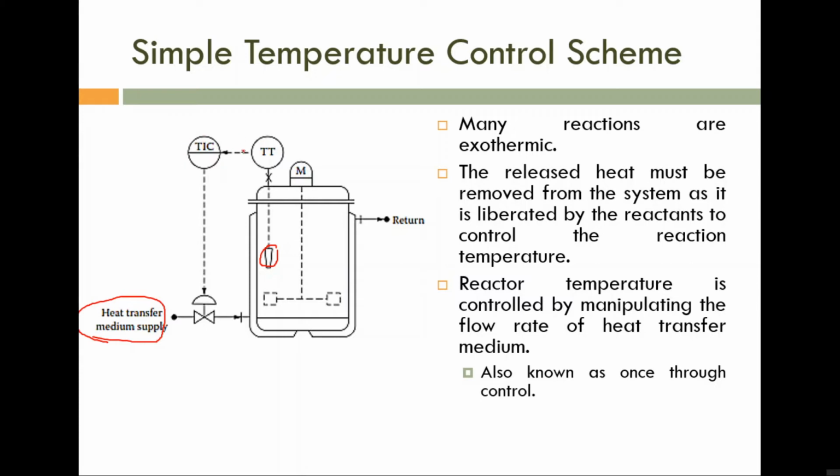Okay. So after receiving this feedback signal, TIC is giving a corrective action to this pneumatically actuated valve. This is a two-way valve. This one is a diaphragm actuator, a pneumatically actuated actuator. But we are giving an electrical signal. Here we have a pneumatic actuator. So definitely an I2P converter is there, that is understood. That one is not shown here because that is not so important. We can assume that if you are using a pneumatic actuator and giving an electrical signal, definitely an I2P converter is there. Without that, we can't operate it.